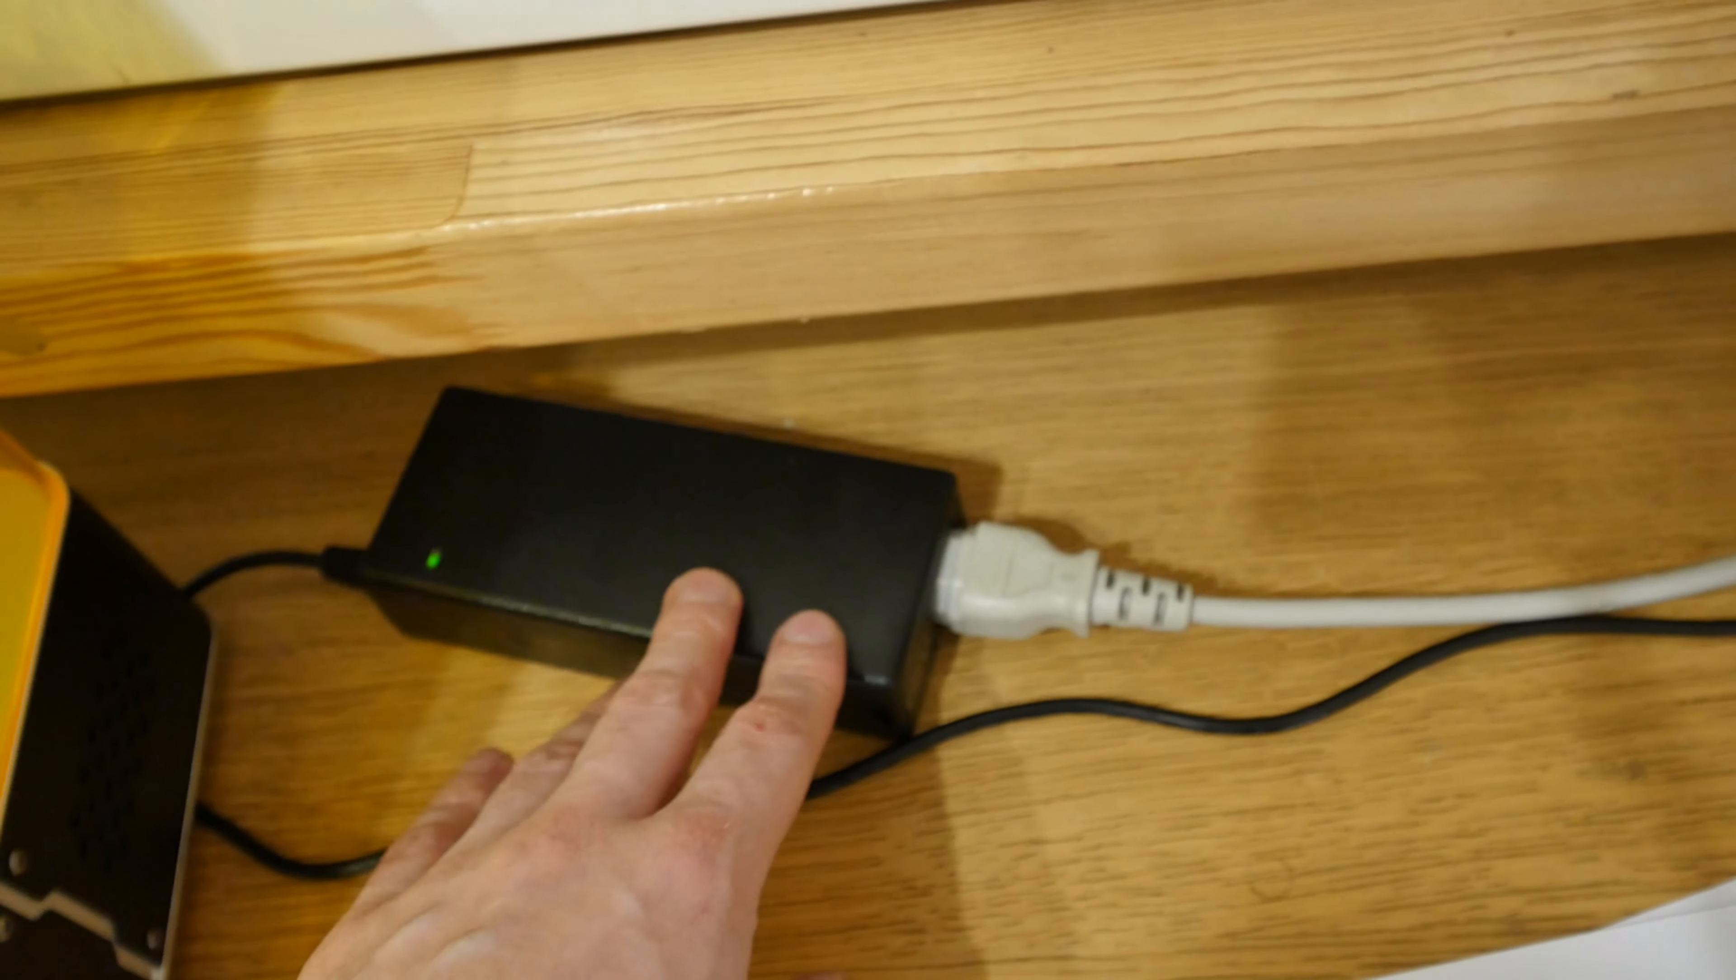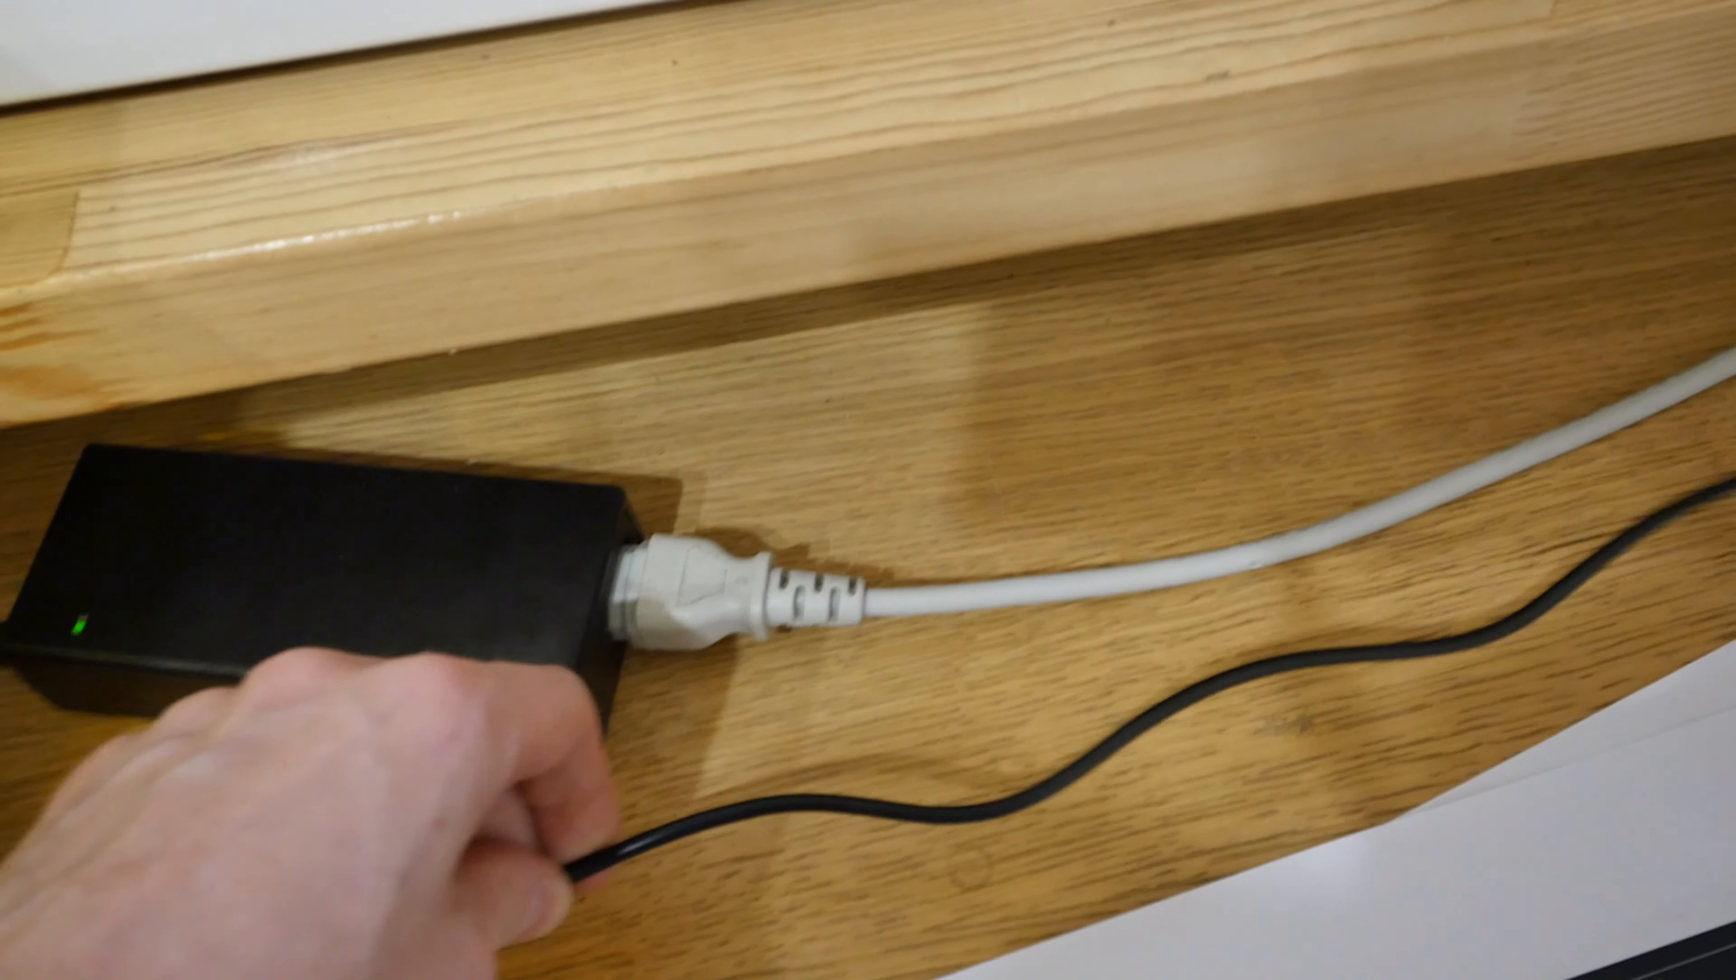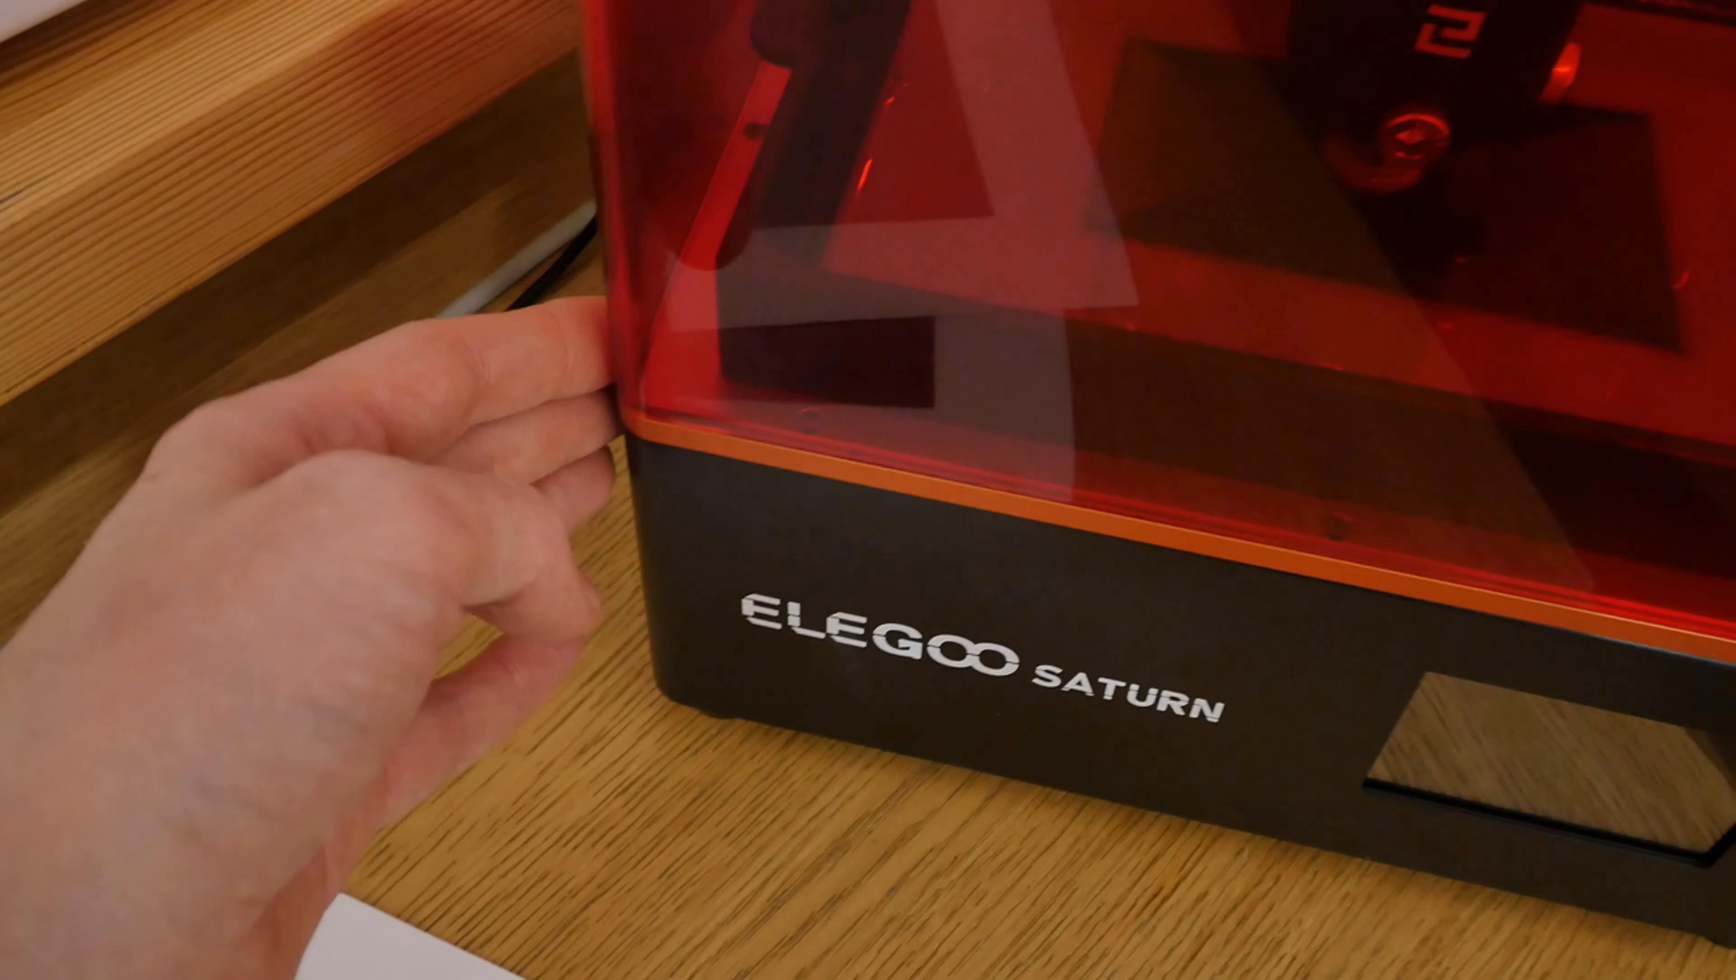And this power supply does have ground earth connected to the ground or zero wire, let's say zero volt wire, but it's not connected to the case. And this is the problem.